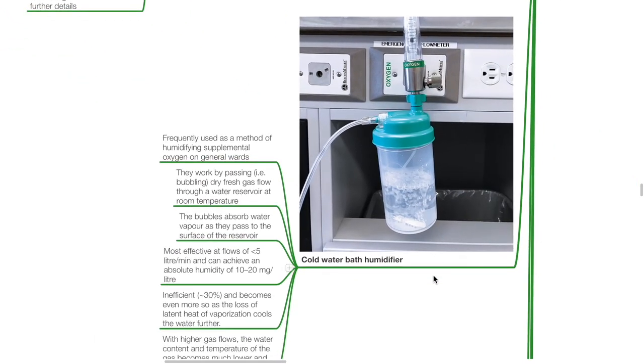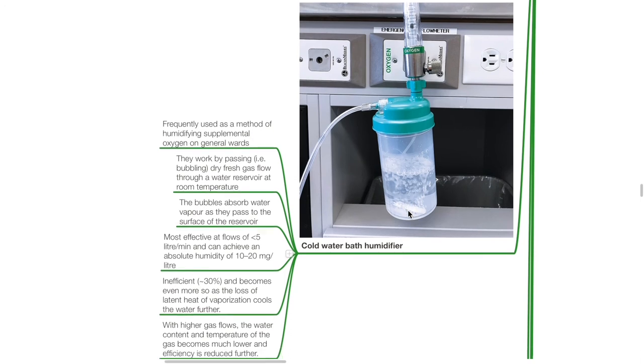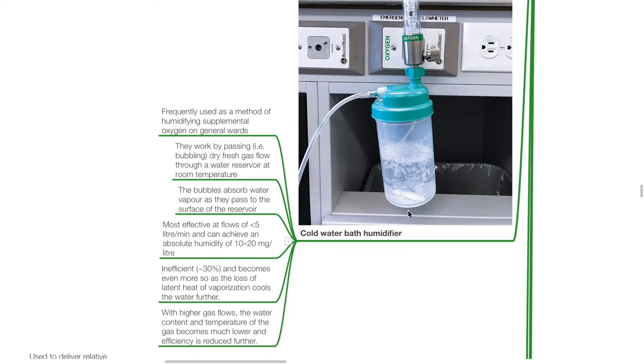The cold water bath humidifier is frequently used as a method of humidifying supplemental oxygen in general wards. It works by passing or bubbling dry fresh gas flow through a water reservoir at room temperature; the bubbles absorb water vapor as they pass to the surface. It is most effective at flows of less than 5 L/min and can achieve an absolute humidity of 10–20 mg/L. It is inefficient and becomes more so as the loss of latent heat of vaporization cools the water further. With higher gas flows, water content and temperature of the gas become much lower and efficiency is reduced further.